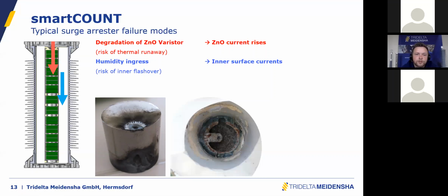Second, and in my opinion most common, breakdown reason for breakdown of a surge arrester is humidity ingress. So you might have a surge arrester which is pretty old, and the sealing system is not as fresh anymore, and gaskets have been aging, or something went wrong during manufacturing, then you have the risk that air and humidity ingresses into the surge arrester housing, and you will quickly have some humidity condensating on the inner surface of the porcelain housing or the fiberglass housing, or maybe also on the zinc oxide column. And if you have a humid layer inside, of course, you run the risk of an inner flashover, and you also get inner surface currents.